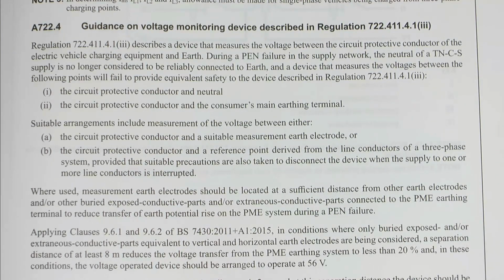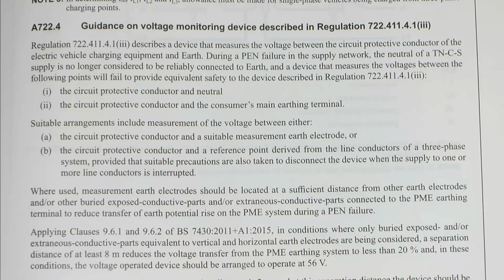This is new, and this regulation describes a device that measures the voltage between the circuit protective conductor of the electric supply vehicle and the earth. During a protective earth neutral failure in the supply network, the neutral of the TNCS supply is no longer considered to be reliably connected to earth, and a device that measures the voltages between the following points will fail to provide equivalent safety to the device described.